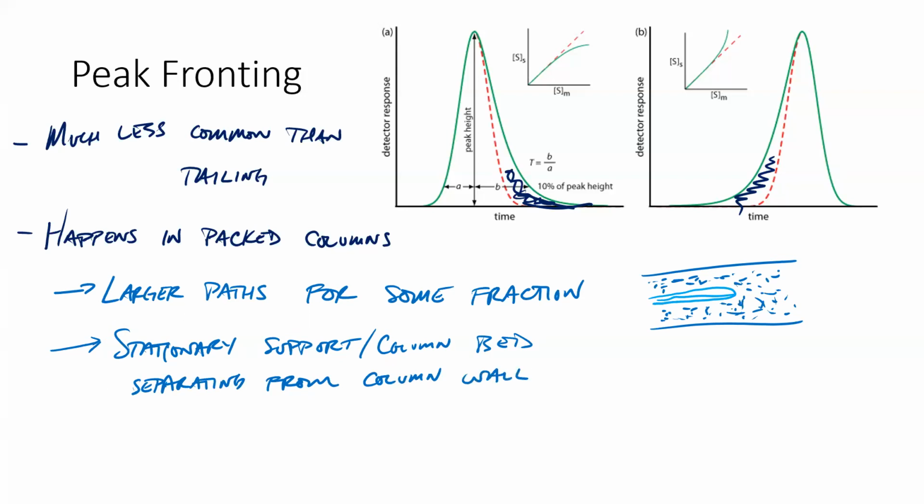And again, this has to do with column age. Over time, they pack these columns very, very well, but they don't run them for 10,000 cycles or something. As you keep flowing mobile phase through it, and as they live through 6 months of vibrations or whatever, there's bound to be a little bit of settling inside that column, a little bit of compression due to the force of that mobile phase moving through it constantly. And so you get some of these issues.